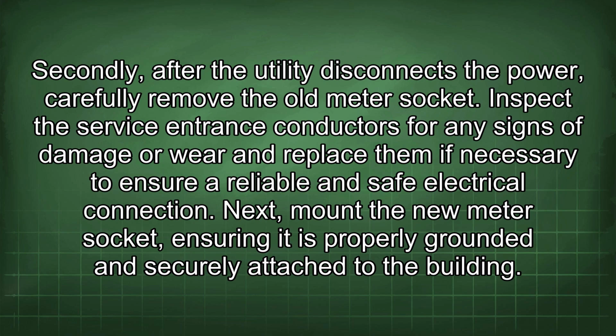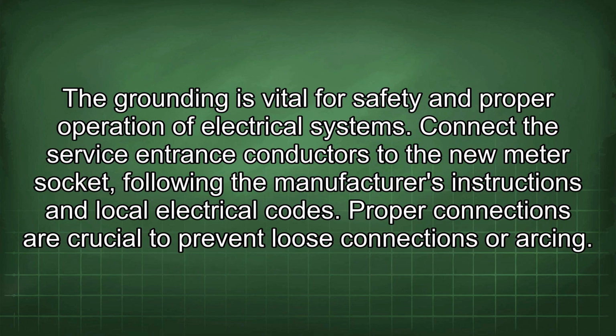Next, mount the new meter socket, ensuring it is properly grounded and securely attached to the building. The grounding is vital for safety and proper operation of electrical systems. Connect the service entrance conductors to the new meter socket following the manufacturer's instructions and local electrical codes. Proper connections are crucial to prevent loose connections or arcing.